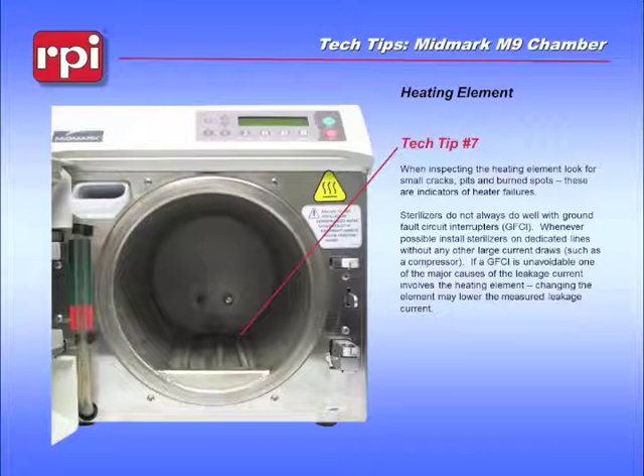We have a heating element on the bottom. The heating element can become cracked. It can become rusted. It can become bent, damaged. You can develop wear spots in it. You want to replace that heating element if you see any of that occurring. You do not want to put a sterilizer on a GFCI breaker because this heating element can develop leakage current through the walls of the heating element, through the walls of the sterilizer, and it will trip a GFCI.